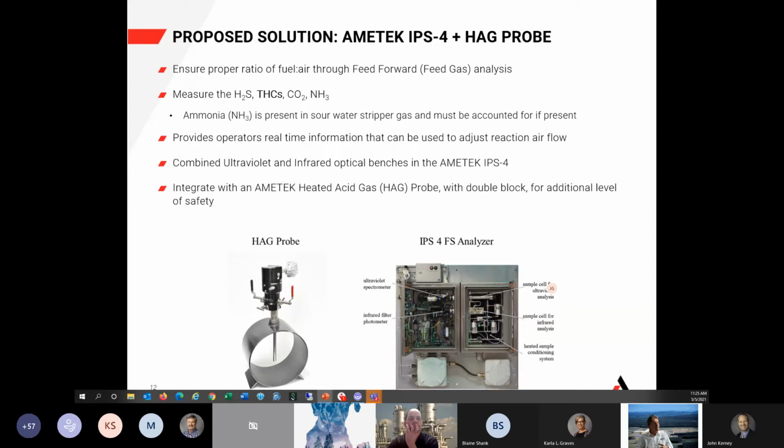Of course, I can separate all the hydrocarbons and give them as a discrete signal, and I know exactly how much methane, how much propane will come. But what do I do with it? If I go that way, it will take 3, 4, 5 minutes analytical time to analyze it. What happens in that time? I will have my answer already from my air demand analyzer. So any analysis you do about the total hydrocarbons to be used in a control has to be faster than the signal comes from your air demand analyzer.